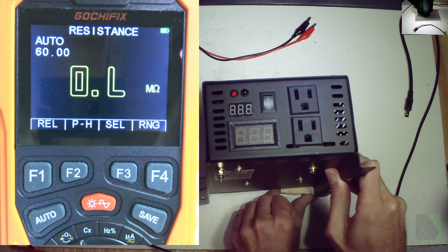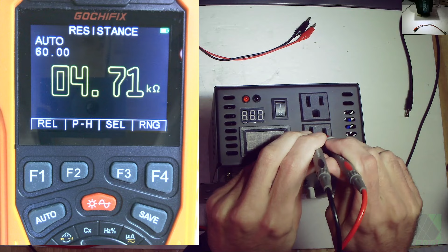It's going to need to be opened up and repaired. Another trick is you can check both outlets to see if both have an open circuit. Stick the probes in here and if you get the same exact reading on both, there's probably nothing wrong and the outlets are fine. If you get an open circuit on one and not the other, you'll need to open the inverter and find out what went wrong, because probably one of these outlets failed and possibly a wire came loose or something like that. Just something to keep in mind.